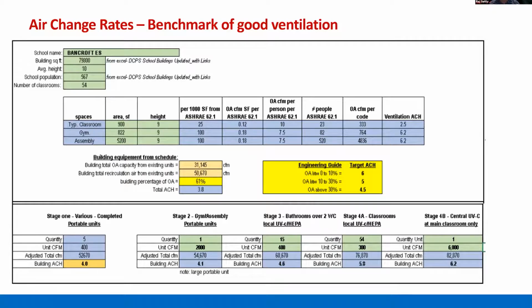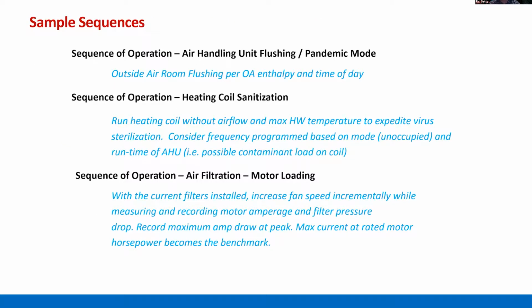So as you start to create your functional performance test, you have to step back one step to a hierarchy level and look at the building holistically and not just each unit. I think often we've been too focused on a singular unit rather than seeing how the building will perform from a ventilation criteria standpoint holistically. So that's going to be another FPT you should be thinking about. These are just some sample sequences. Mike, you want to just go over a couple, then I can finish it off?